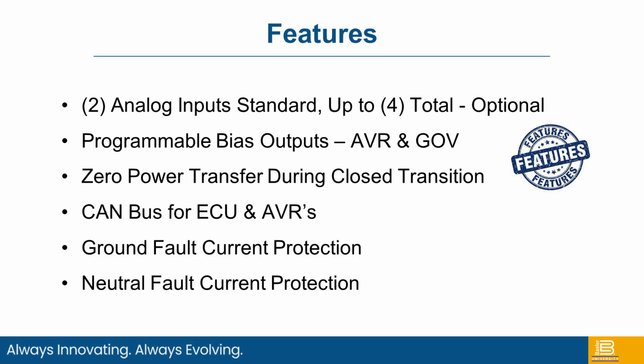We can also do zero power transfer, which means basically when you're paralleling the utility, the HD will bring the generator into sync, close the generator circuit breaker, and basically it goes to a zero power transfer and then increases load to whether you want to do a base load or whether you're going to do a closed transition. It can also do the same thing on the way down. So as you start to unload the gen and return the power back to utility, it will go through a zero power transfer. Those settings are also adjustable.